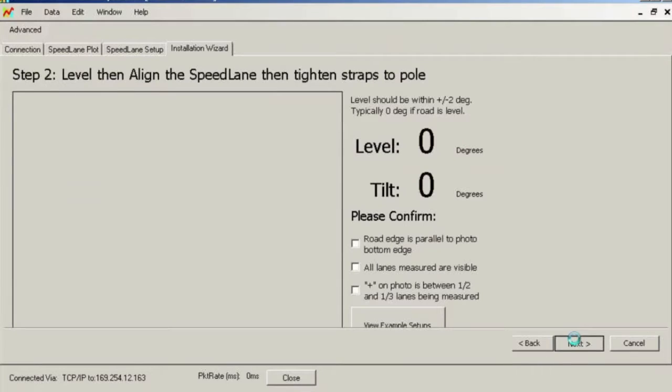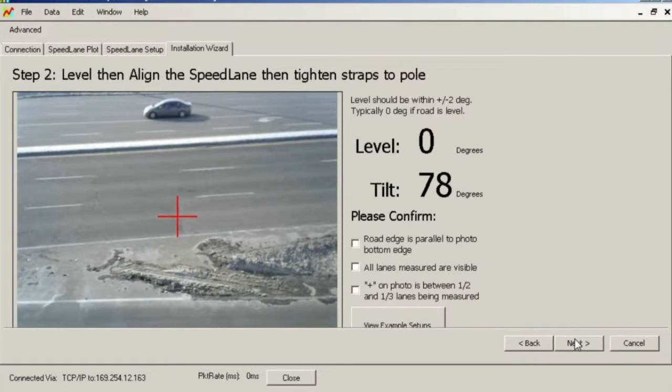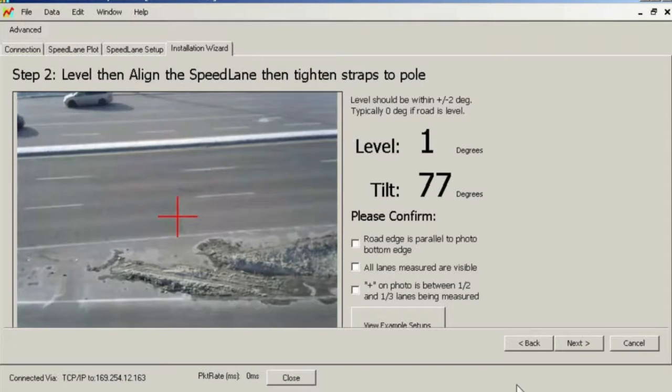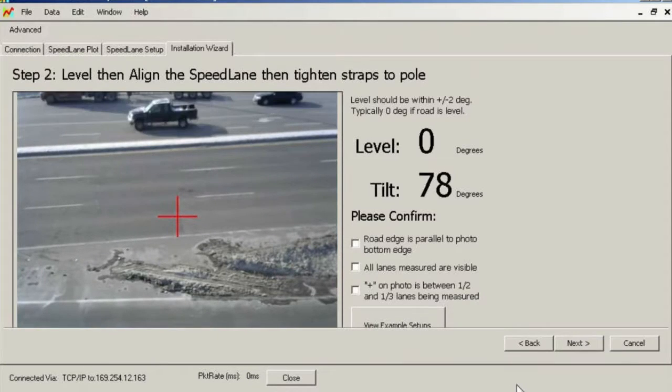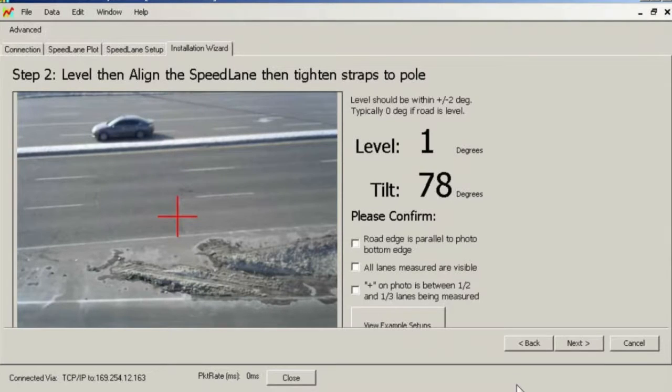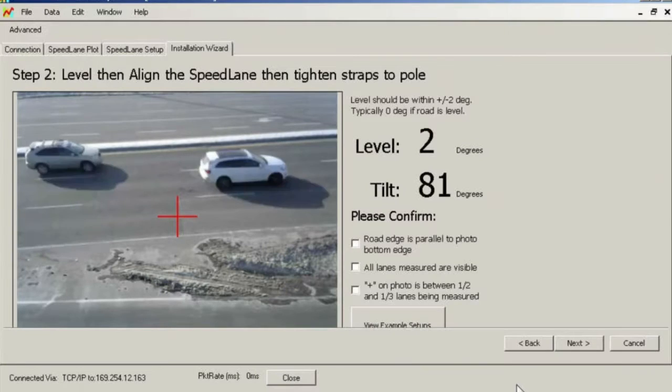This screen shows the camera view as well as the level and tilt readings. These are automatically refreshed every few seconds for convenience. You may consider bringing along handheld radios to communicate with the installer on the bucket truck. While you watch the camera image and level readings from your vehicle, you will be able to provide feedback on how to adjust the unit as it is strapped to the pole.